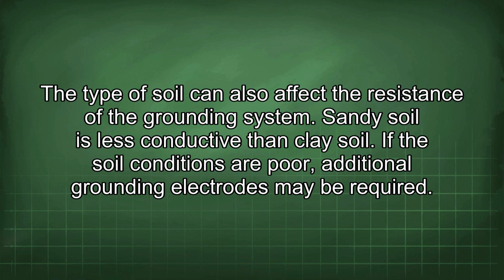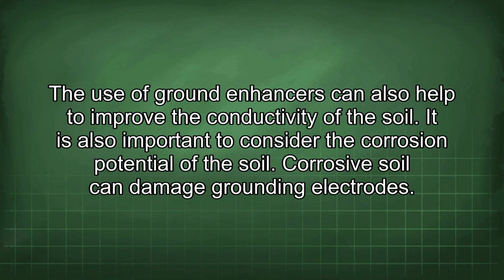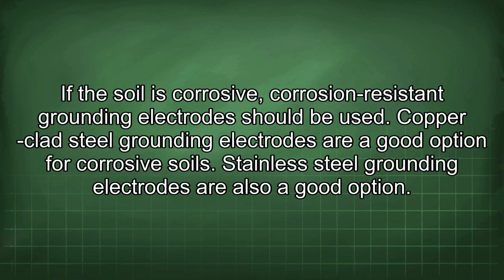If the soil conditions are poor, additional grounding electrodes may be required. The use of ground enhancers can also help to improve the conductivity of the soil. It is also important to consider the corrosion potential of the soil. Corrosive soil can damage grounding electrodes. If the soil is corrosive, corrosion-resistant grounding electrodes should be used. Copper-clad steel grounding electrodes are a good option for corrosive soils. Stainless steel grounding electrodes are also a good option.